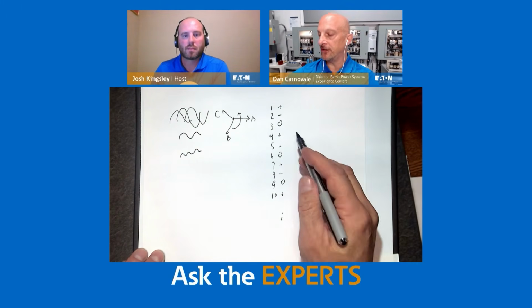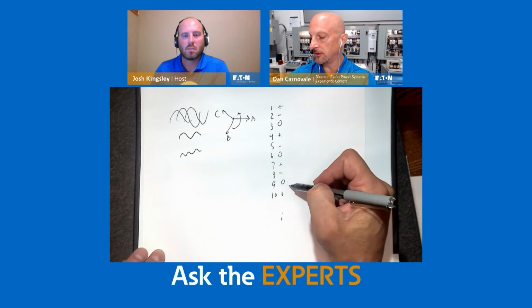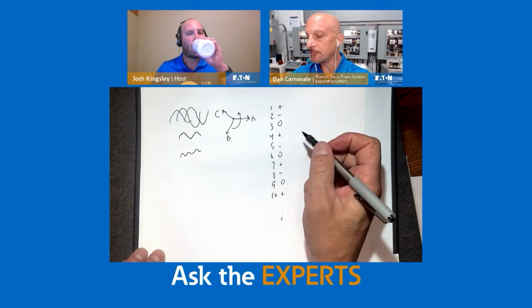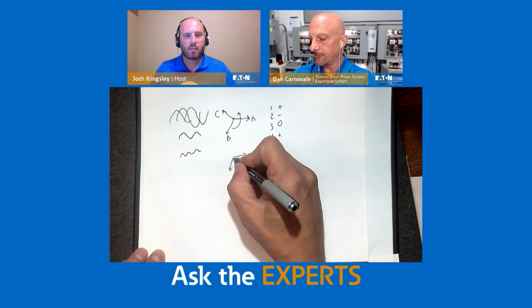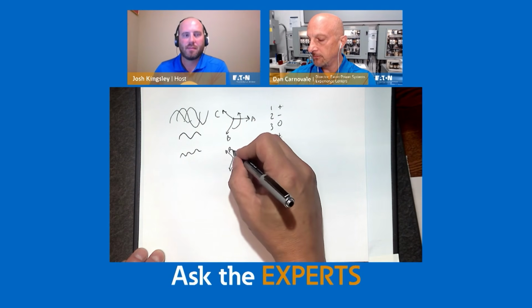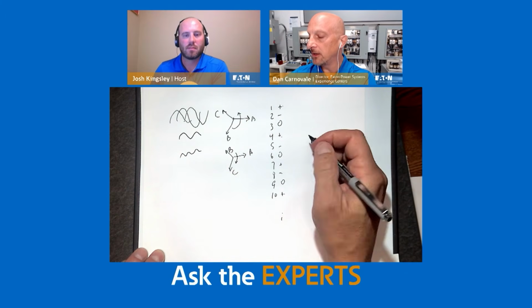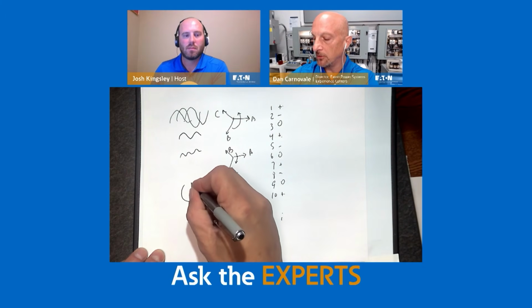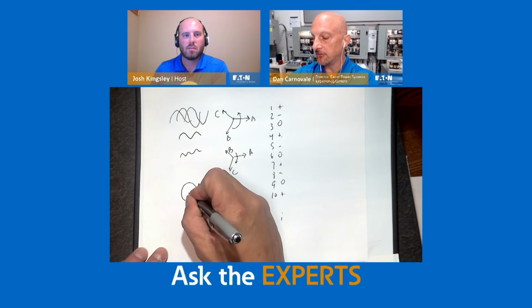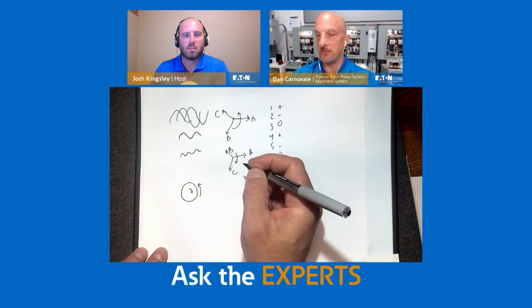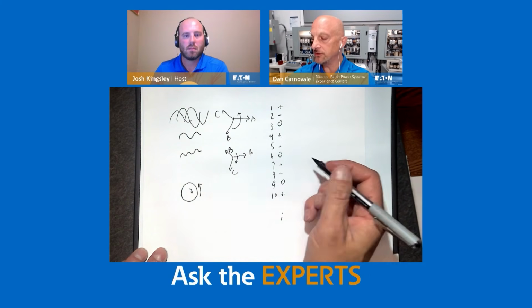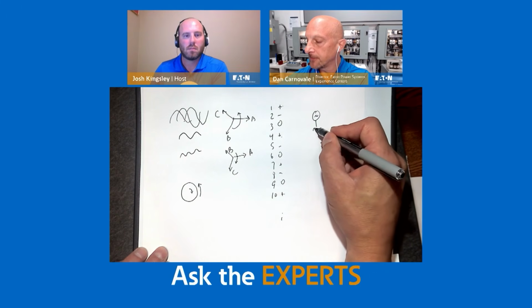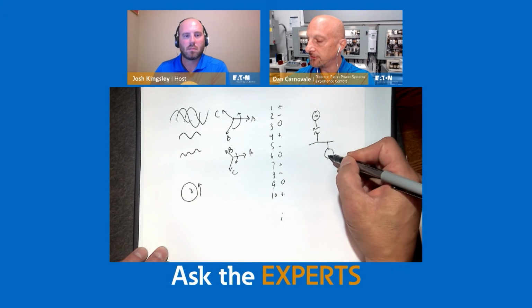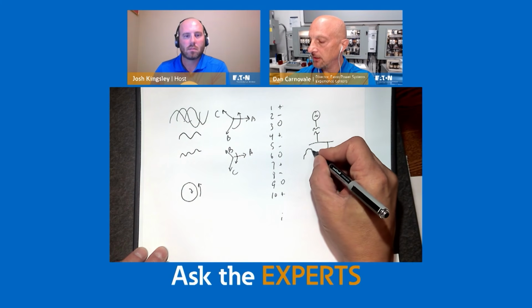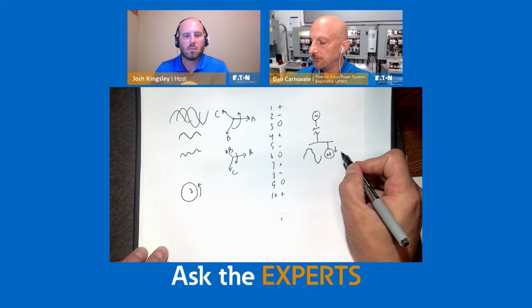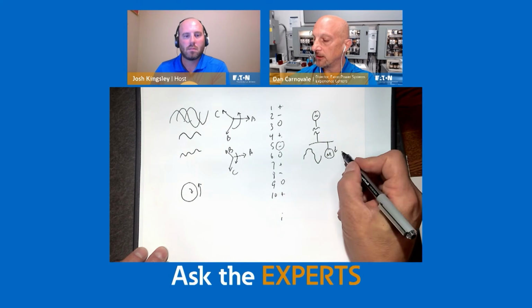Positive sequence harmonics, which are this one, this one, this one, act like the 60 hertz stuff. Negative sequence harmonics are kind of like A, C, B. Say we have a motor that spins, and the 60 hertz is making it spin this way. The negative sequence harmonics kind of make the motor want to spin the opposite way. So say I have enough voltage distortion on my bus here that even an across-the-line motor might see a voltage that looks like that, which means it's going to draw a current that might be, for example, a negative sequence harmonic, like the fifth harmonic.